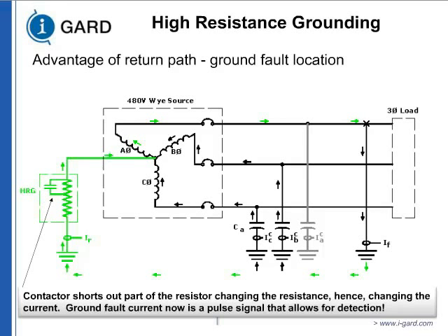So a pulsing contactor came in. All a pulsing contactor does is give you 40 pulses per minute. And you can check the pulsing current, where it is going. The contactor shorts out part of it, or you can have multiple resistors. That technology is one or the other. Technically, what I'm aware of, you have 5 resistors in there. Then when you want to pulse it, you only have less in circuit to give you a higher current. And that's how the detection scheme came in. That was a very important tool for operating engineers. Now we could make an effort to avoid a second ground fault without shutting down like we used to do on Delta.